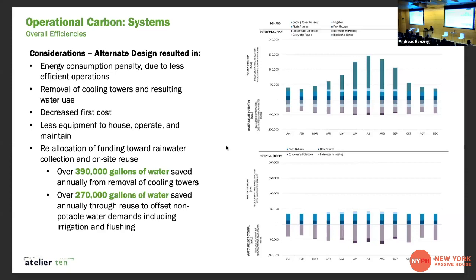This alternate design, an all air source heat pump design, was shown to better serve the project when considering a holistic sustainability approach instead of simply zoning in on operational energy efficiency. So while taking a slight penalty due to marginally less efficient operations, the design was able to remove a significant amount of equipment from valuable roof area, including cooling towers.